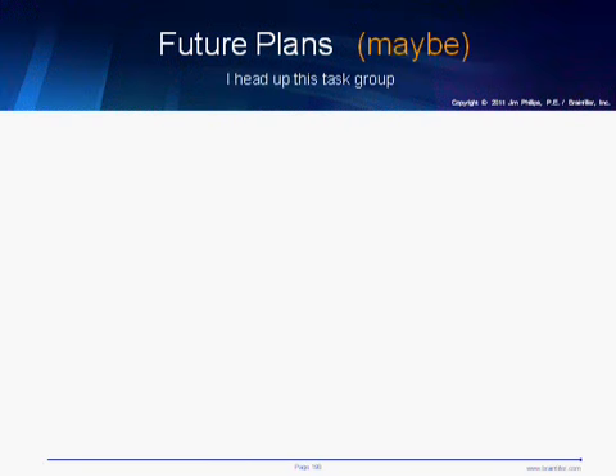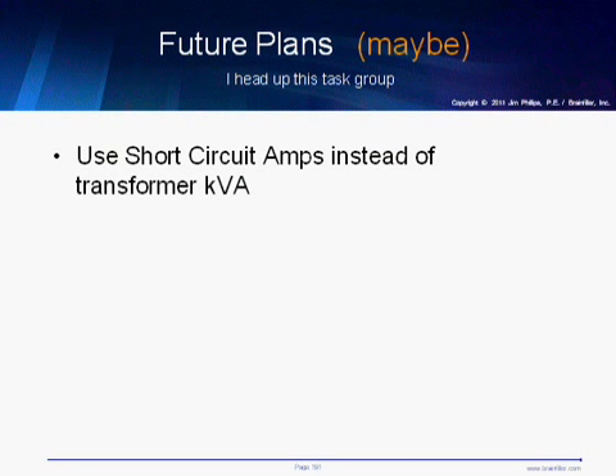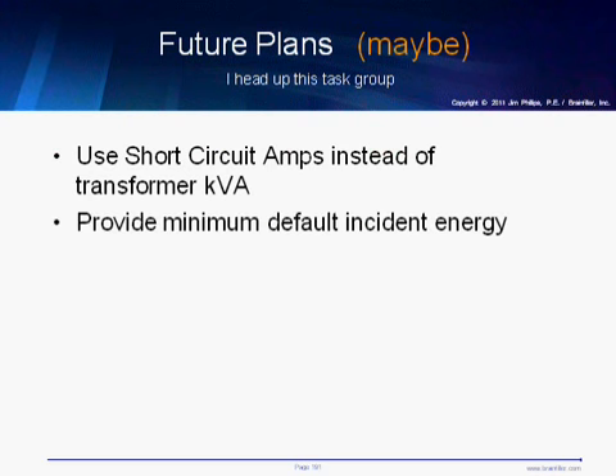Where I believe this is going, and this is not coming from any official source, is that the 125 kVA transformer exception, and I'm actually heading that task group up, is most likely, when it is revised, going to be more of a short circuit current rather than a kVA, because short circuit current is easily applied. We've even been talking about maybe having a default energy. This is all just table discussion, because one of the problems with the exception is that if you have a circuit that's exempt, you throw your hands up in the air and say, okay, what does that mean? What do I do here? And that question was never answered.